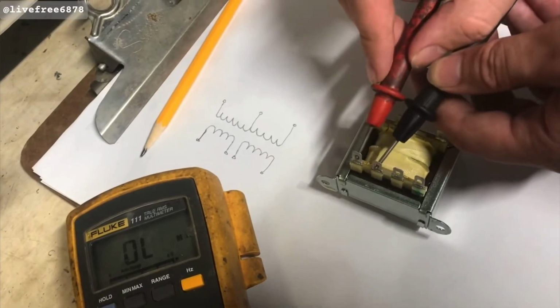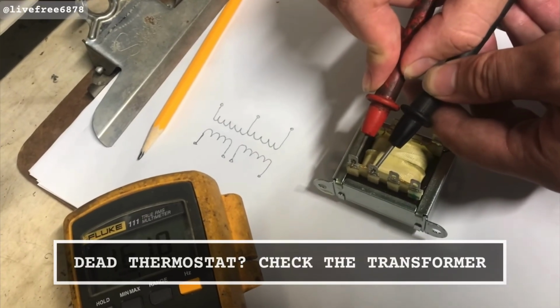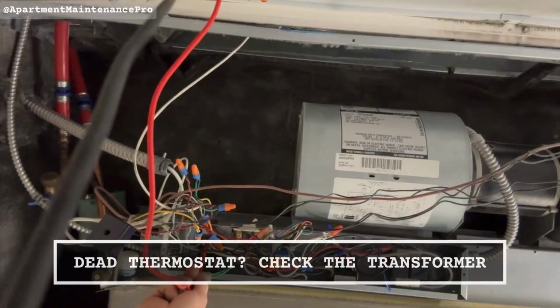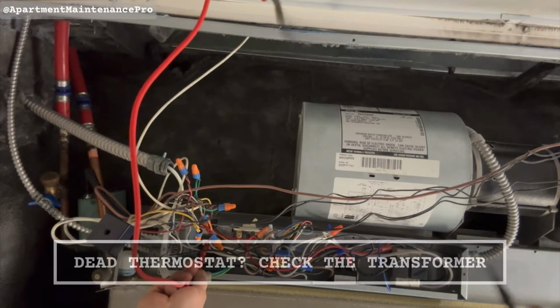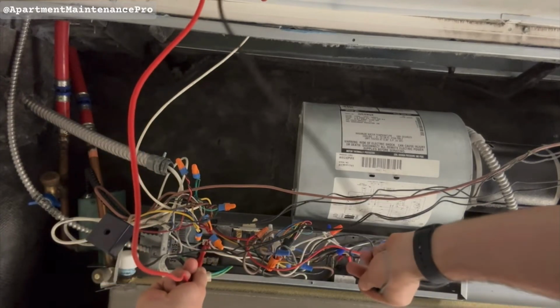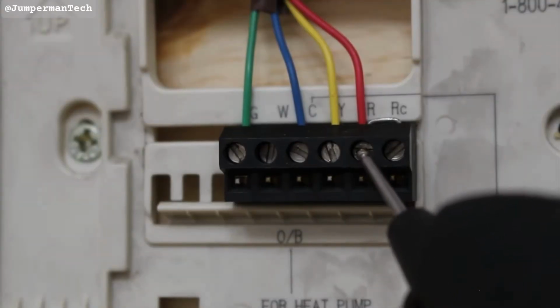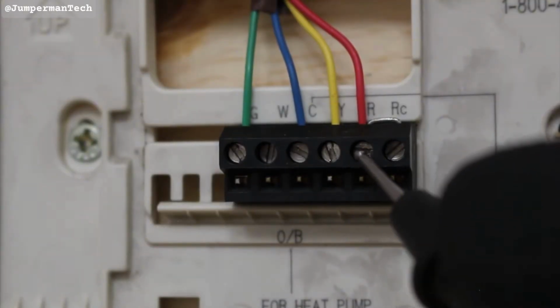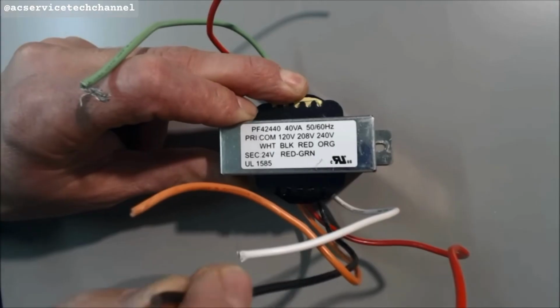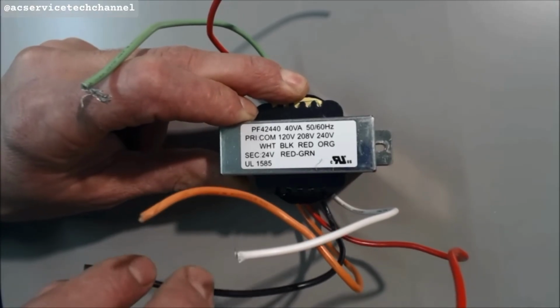Number 11. When the thermostat goes dead and nothing happens at the air handler, listen at the unit. A faint hum from the low-voltage transformer means it's alive and the problem is upstream. Silence means the transformer is fried. $25 part, 5-minute swap. Most service calls for dead thermostats are this.